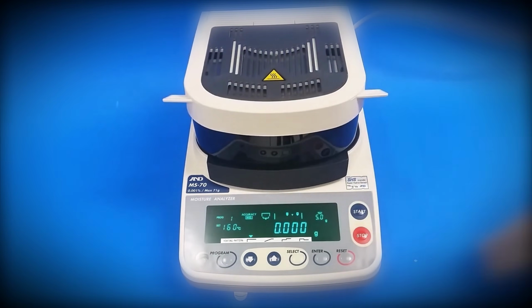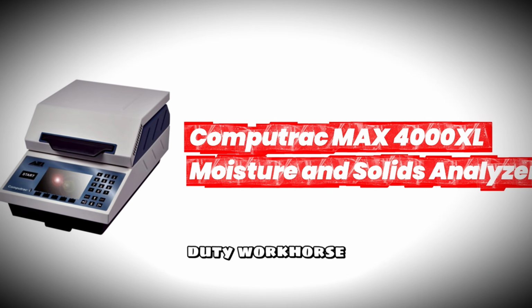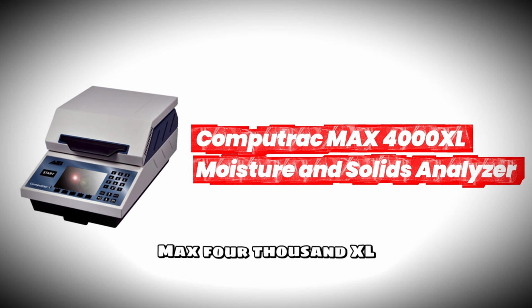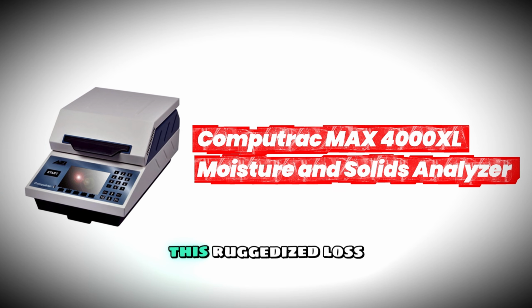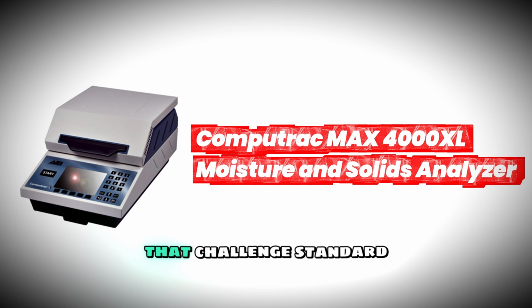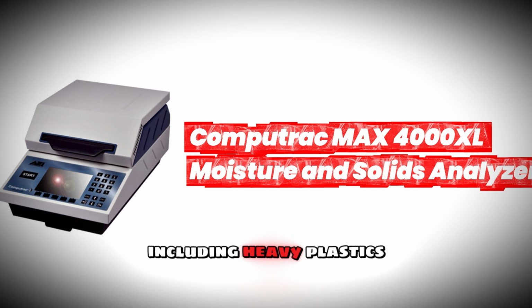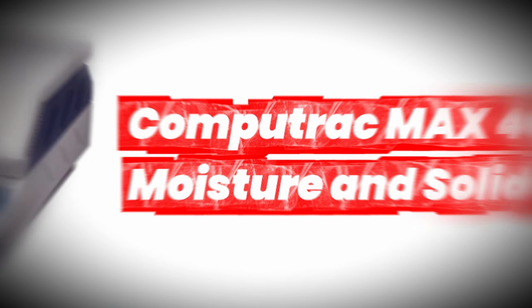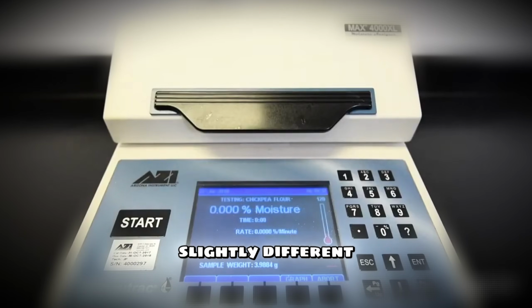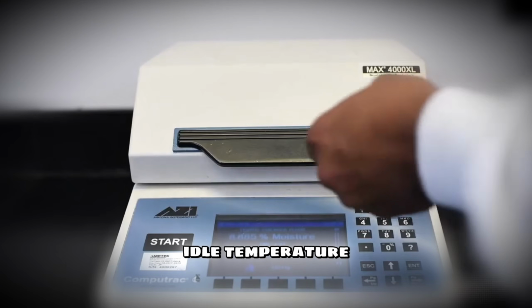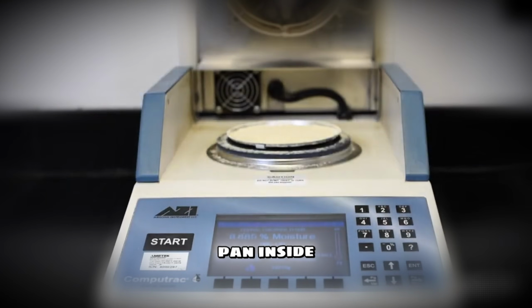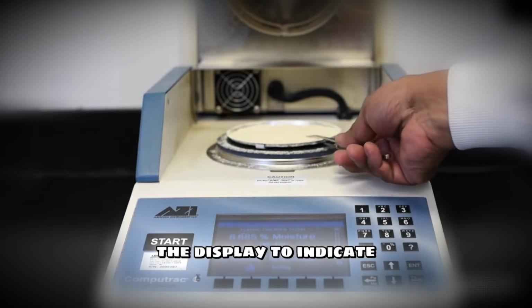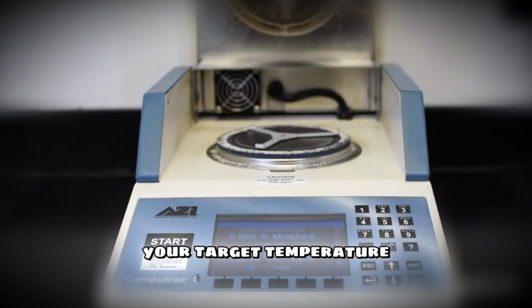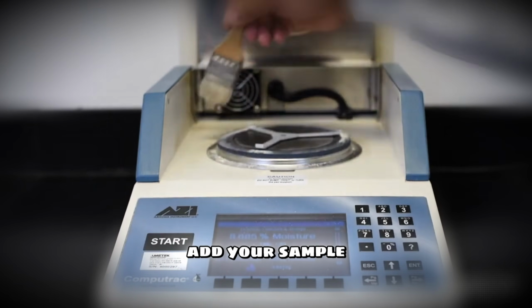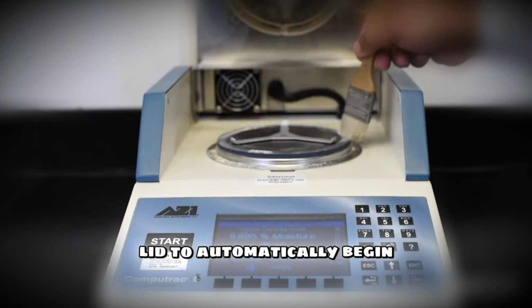Finally, the heavy-duty workhorse, the Computrac MAX 4000XL. This ruggedized loss-on-drying instrument is purpose-built to handle the toughest materials that challenge standard optical systems, including heavy plastics and thick asphalts. The workflow is slightly different. First, let the chamber reach its idle temperature. Place a clean pan inside and wait for the display to indicate it is within 2 degrees of your target temperature. Once ready, quickly add your sample and close the lid to automatically begin.